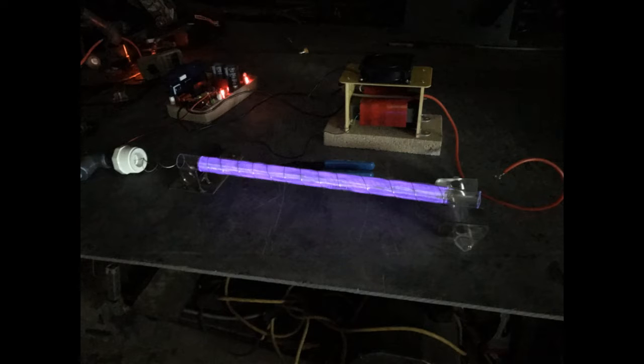One thing I did notice during testing was that the more you increase the pressure, the less current draw from the ozone power supply. So that's not necessarily a good thing—we may have to crank up the power a little bit to compensate for that. I just wanted to warn you that when we pressure up to about 50 psi, the current draw on my initial setting was reduced by about 50%.